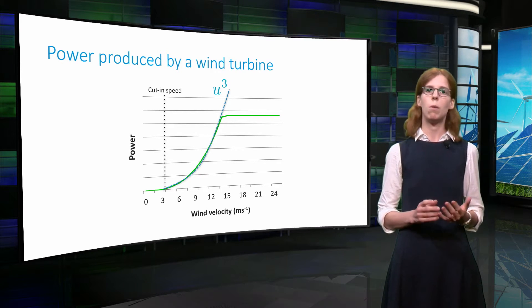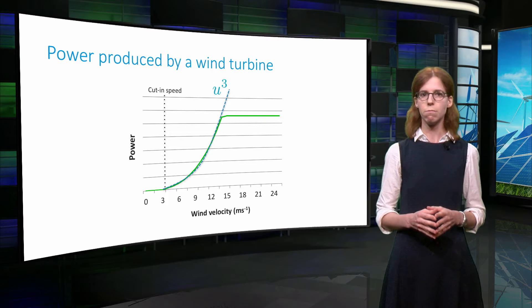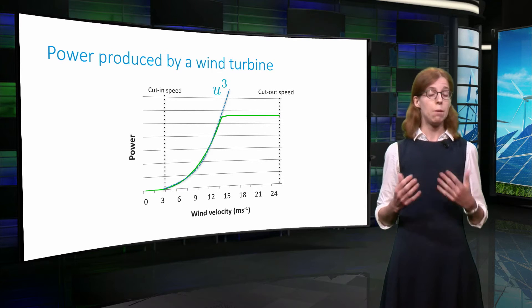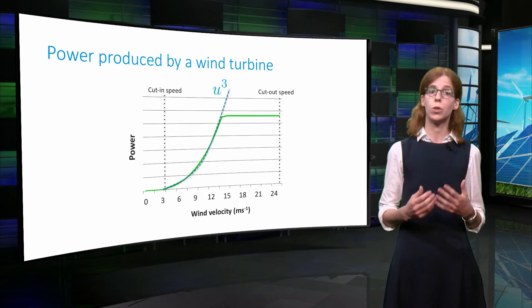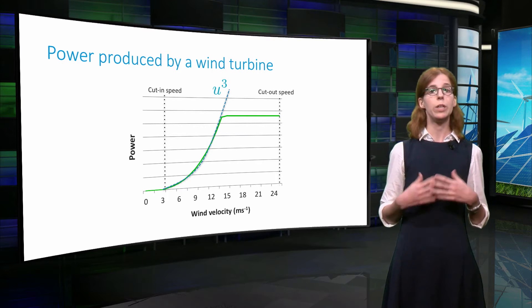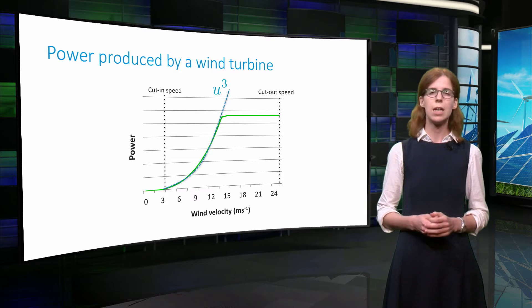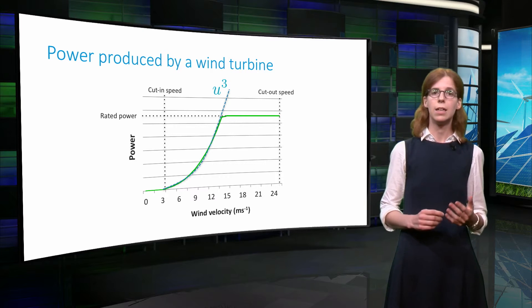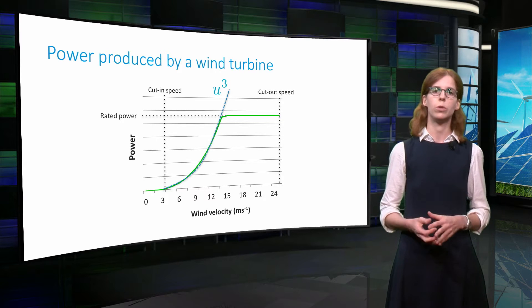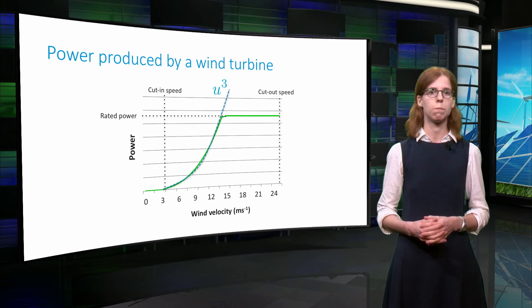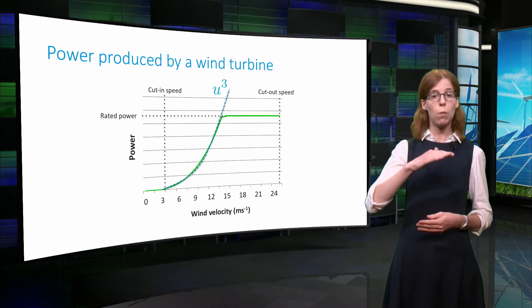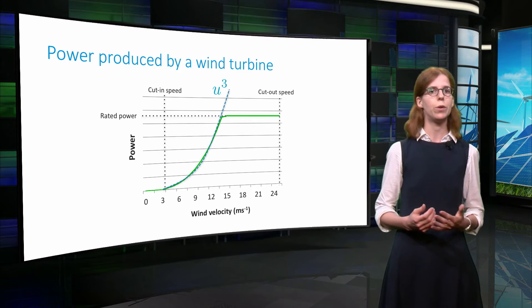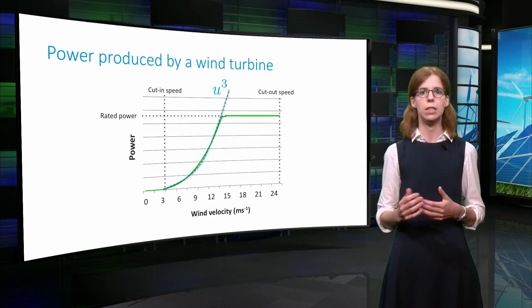The cut-in speed is typically about 3 to 4 m/s. On the other hand, if the wind is very strong, the loads on the rotor can become too large. Therefore, the so-called cut-out speed is the maximum wind speed at which power can be safely produced, and this lies typically around 25 m/s. Finally, the electrical generator also imposes a limit on the power that can be output. Just beyond a certain wind speed, the power is limited to a constant value. This value is called the rated power and typically occurs for wind speeds between 12 and 17 m/s.